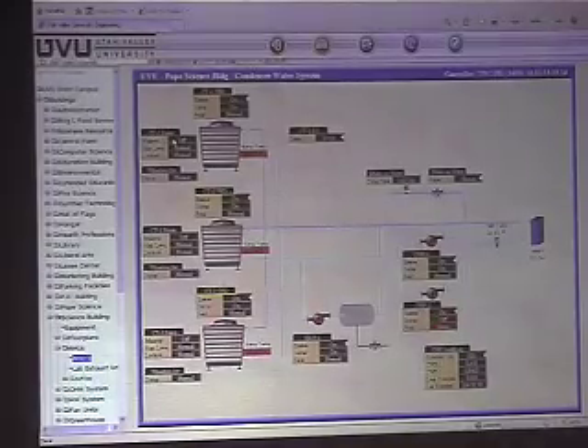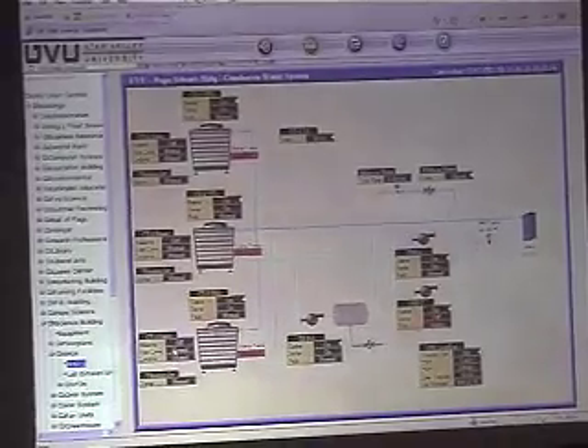So if you see that makeup on here, that means that the water level is somewhere between those 2 sensors, and it's calling for it to make up. And then you've got your high level here, which is the highest sensor, which means your water obviously is just too high in the tower, which we've got interlocked to the valve, so it'll shut it off in case something with the makeup sensor goes bad. That way you don't spill over onto your overflow and just dump water onto your roof. So there's a set of those sensors for each tower, so they're all represented here. If any of these makeups turn on, it'll open up the makeup water valve right here.